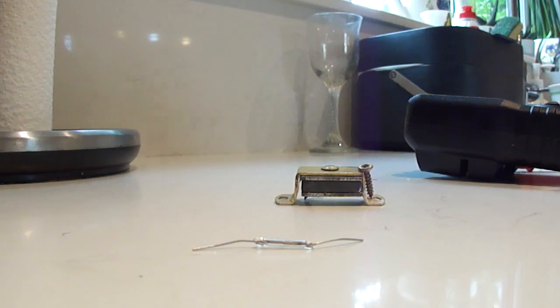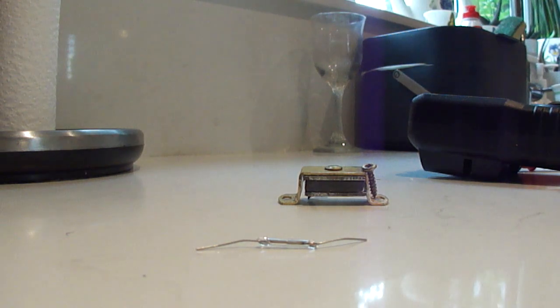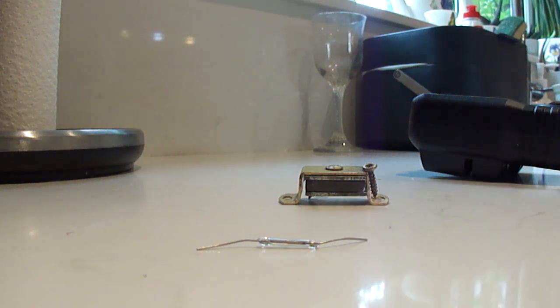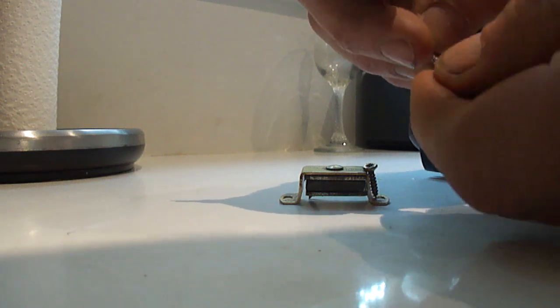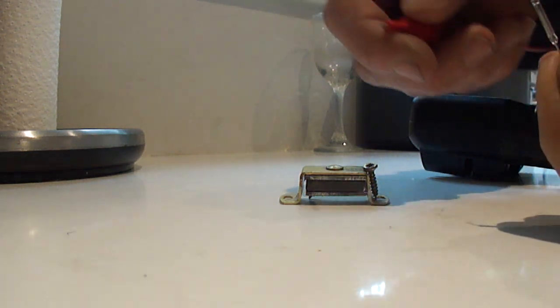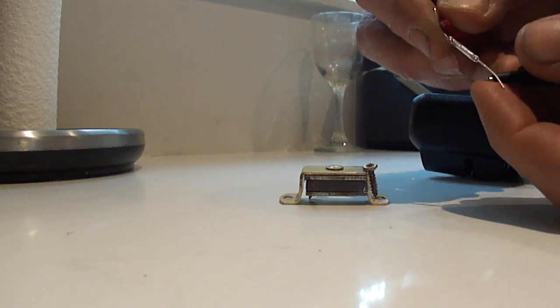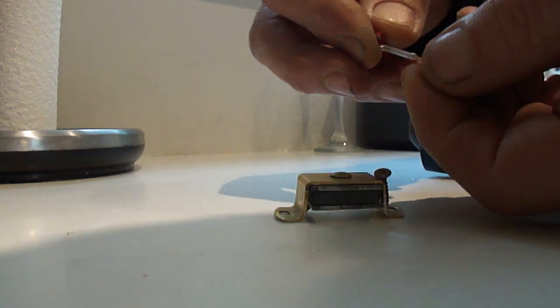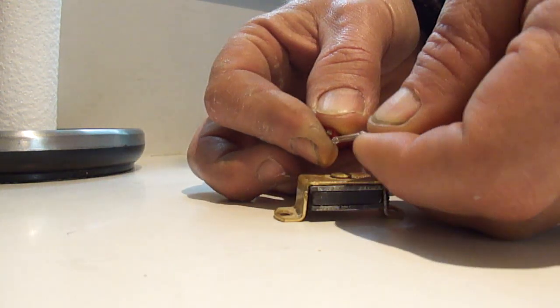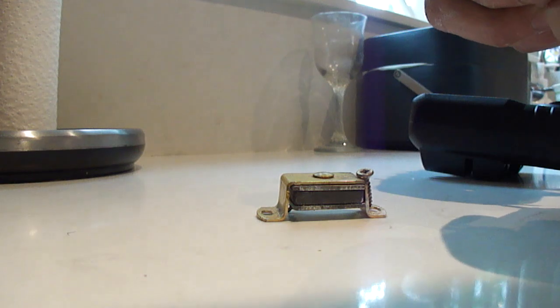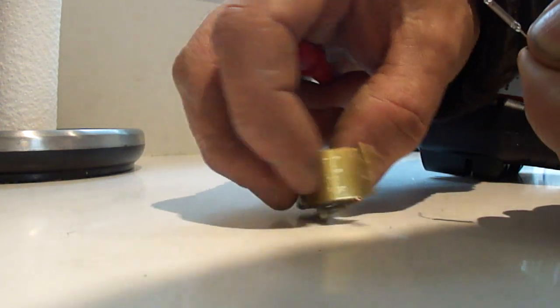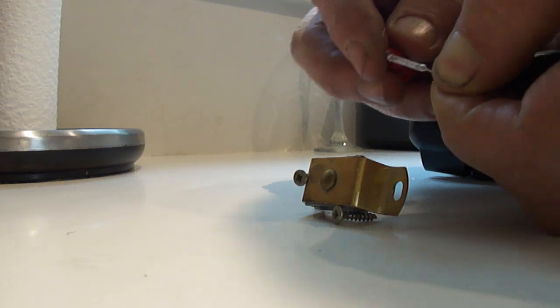To test the old one, leave it on the board obviously. Let me just turn that machine off. All you need to do is put your meter on continuity and then put the probe across the reed switch - now obviously this would have been in the board, it's the same sort of thing - and then bring it in contact with a magnet. Right, let's test the continuity here. Bring it in contact with a magnet and you should hear it beep.